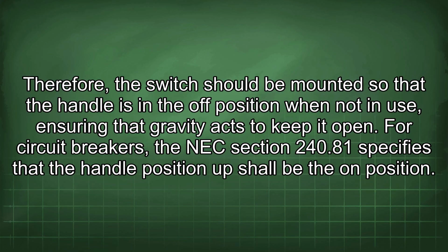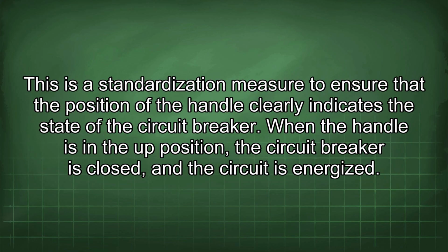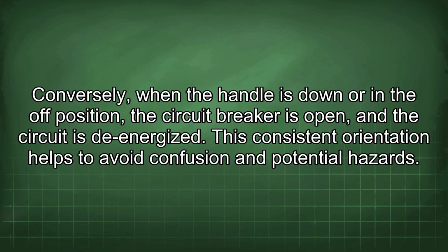For circuit breakers, the NEC Section 240.81 specifies that the handle position up shall be the on position. This is a standardization measure to ensure that the position of the handle clearly indicates the state of the circuit breaker. When the handle is in the up position, the circuit breaker is closed and the circuit is energized. Conversely, when the handle is down or in the off position, the circuit breaker is open and the circuit is de-energized. This consistent orientation helps to avoid confusion and potential hazards.